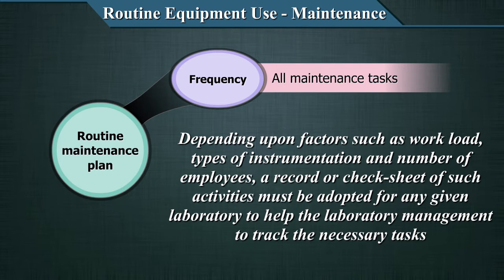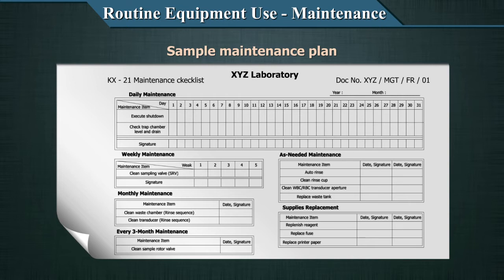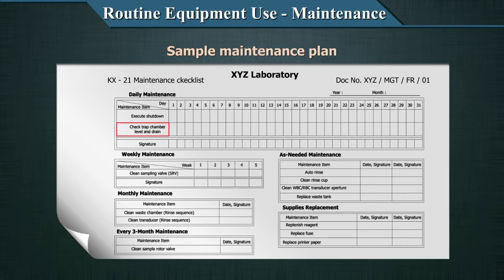We will show you a few formats or maintenance logs for different equipment. Such formats have to be developed for all equipment used in the laboratory. This format is for the daily maintenance of a particular equipment, depicting about 30 to 31 days. Each activity must be done on a daily basis — such as execute shutdown, check the trap chamber, and so on. After the technician completes the task, it has to be checked off with a check mark and signed as evidence of daily maintenance.